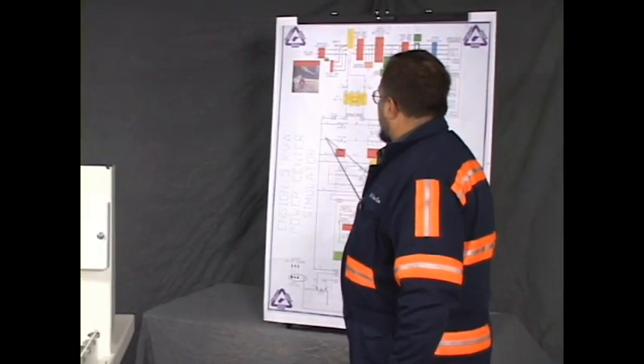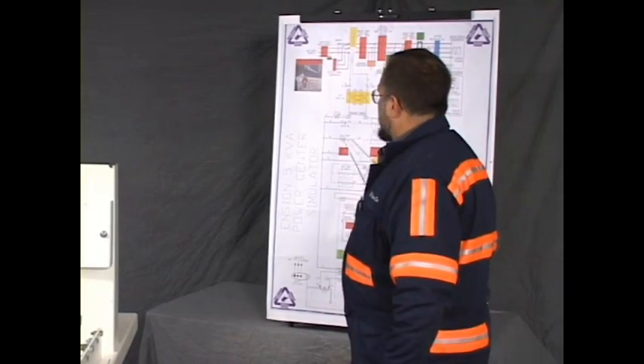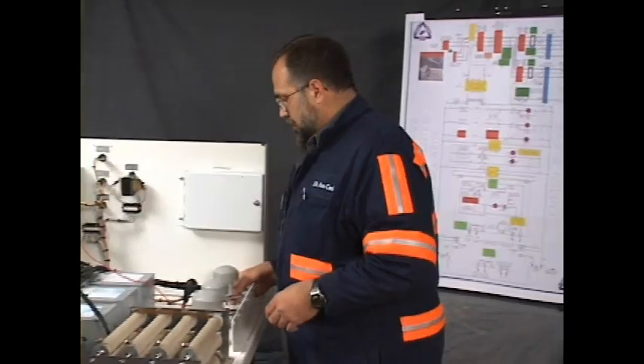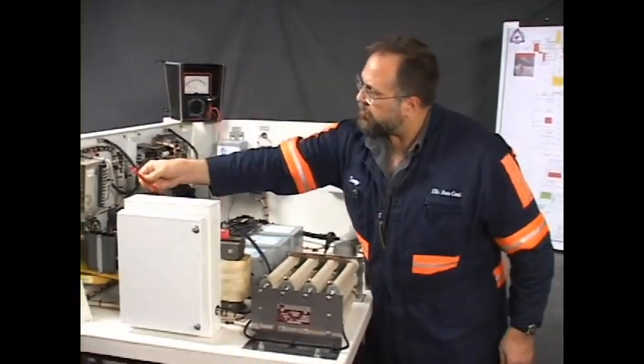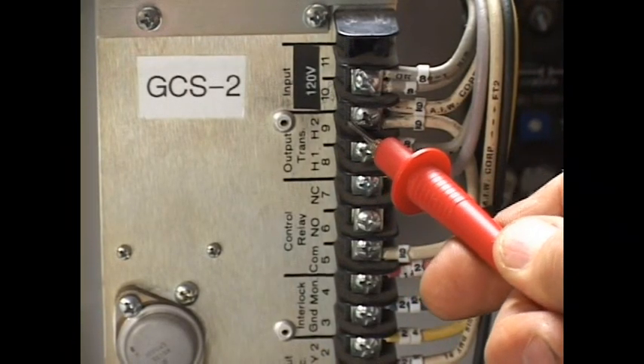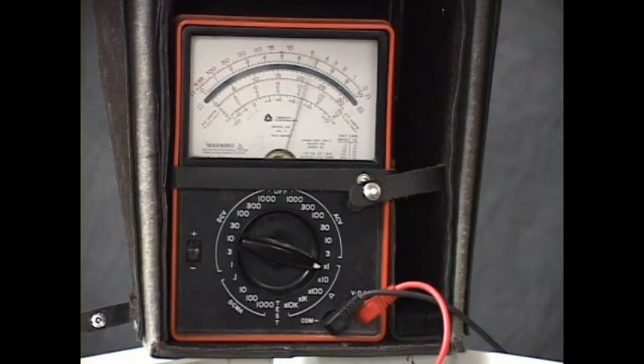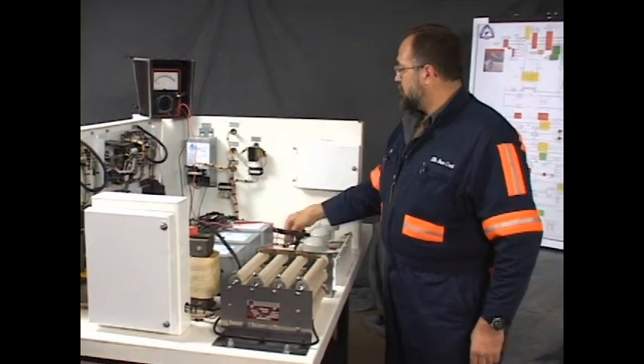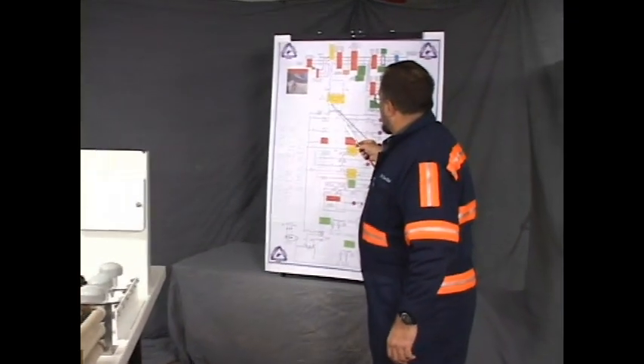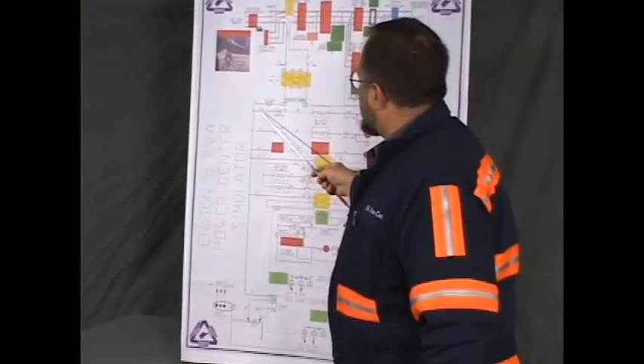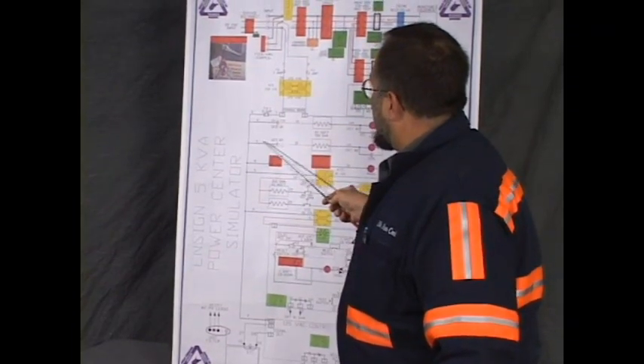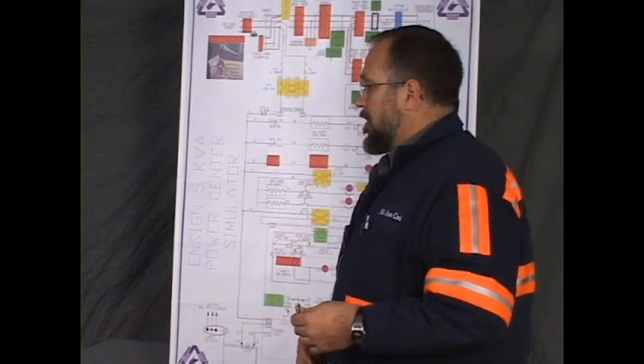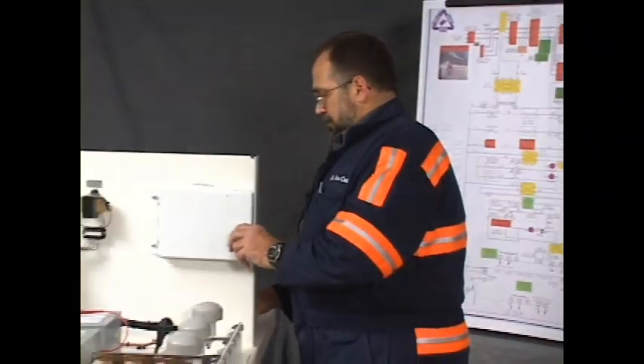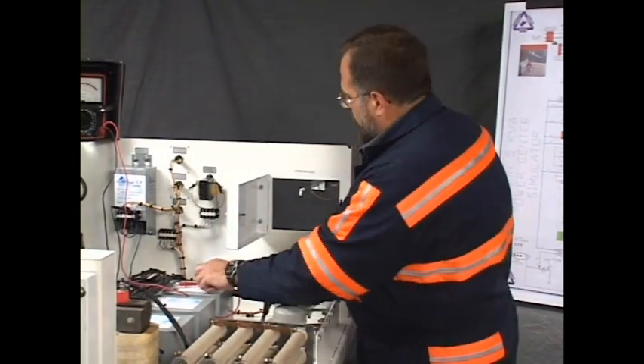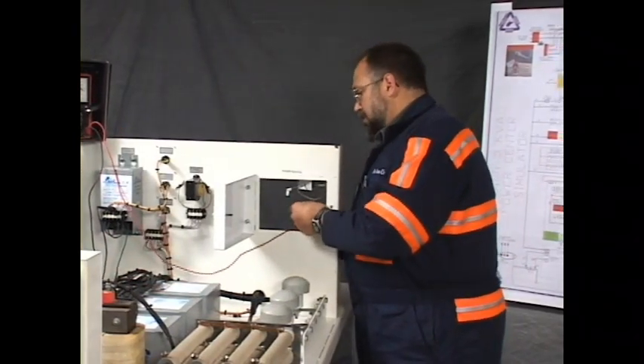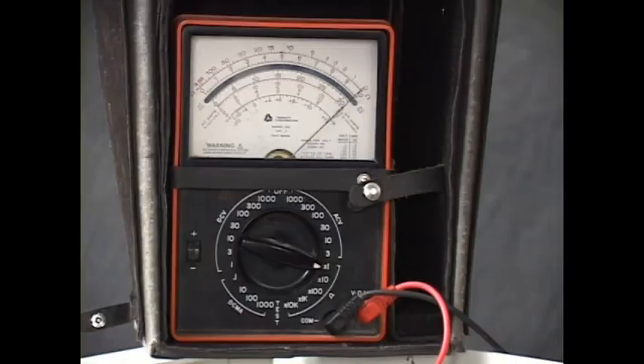Now the next step that we can take, terminal 5 of GCS2. And that would be here, terminal 5, GCS2. As you can see by the meter, we have continuity to there. So this circuit is intact from the probe we have attached here, through the terminal block, through the fuse. We've touched down here, we've touched down here. The next place to check is the door switch. Wire number 9 on the door switch. This is the door switch. We're going to put our probe through and go to 9 here. As you can see, it's good.